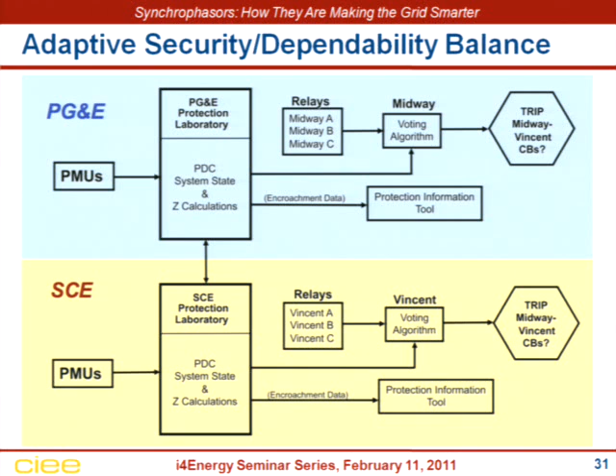And what the voting algorithm says is, I want 2 out of 3 relays to say trip. And otherwise, don't trip. If it's just one relay, it's probably a false trip. And if you look at the probabilities of that, it's very, very high probability that that'll work correctly. So the voting algorithm then comes into play during blackout conditions, and it prevents the relay from tripping falsely and contributing to a blackout. Now, the encroachment data comes into this protection information tool, and I'll show you that in a minute.